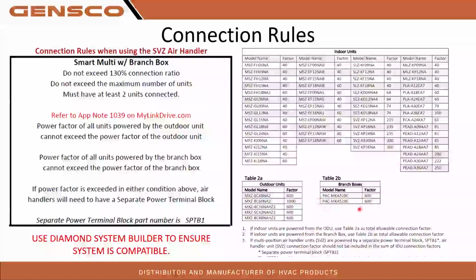What you've got to be careful with is, if you look at your branch box, you have a max power factor of 600. That means if you've got lots of equipment on there, especially ducted units, you need to look at the power factor of that ducted unit. For example, your SVZ 30 and 36 have a power factor of 300, so you can only put a maximum of 2 of these SVZs on your branch box. You can't do any other equipment once you hit that power factor. If you do get up to that max power factor, you'll have to start powering your indoor equipment off of separate power itself, providing a separate circuit to those units using a separate power terminal block. SPTB1 is the part number for it. This provides a circuit inside of your air handler, so you can run a dedicated circuit and go over that power factor, because now that SVZ, if you're doing a separate power supply, is no longer added into that max power factor.